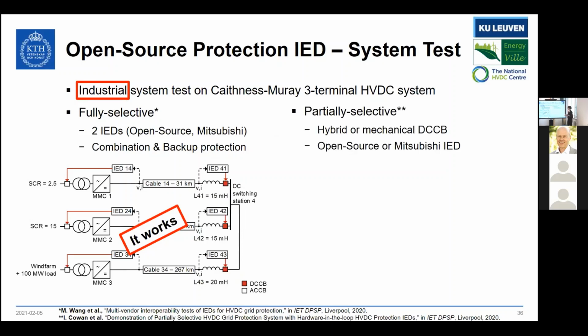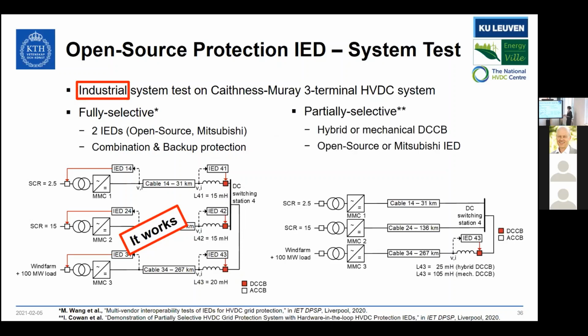But then another study I want to mention is a partially selective study, looking into only one IED installed and one DC circuit breaker, of course, simulated in the real-time simulation. And that's an interesting study because that's closest to what you would do if you're a transmission system operator. So instead of installing 3 DCCBs, it's likely that you want to install only 1 DCCB, and that's why this kind of study is interesting.